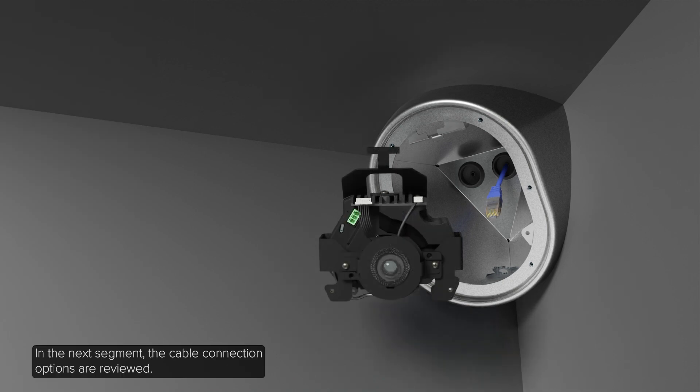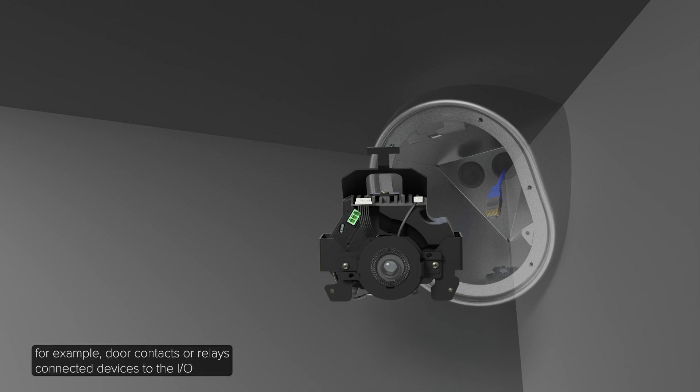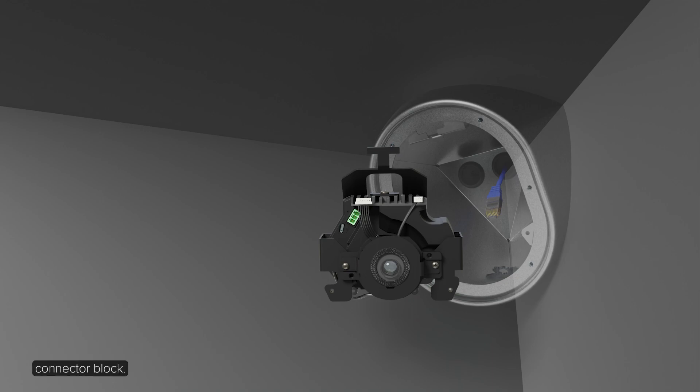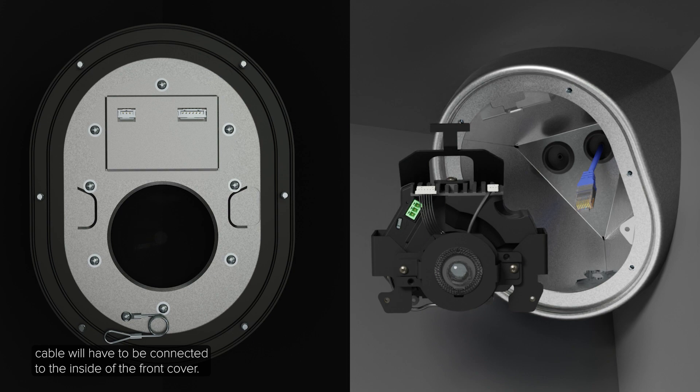In the next segment, the cable connection options are reviewed. If external input or output devices are part of the installation, for example door contacts or relays, connect the devices to the I-O connector block. If the built-in microphone is used, the factory installed audio cable will have to be connected to the inside of the front cover.